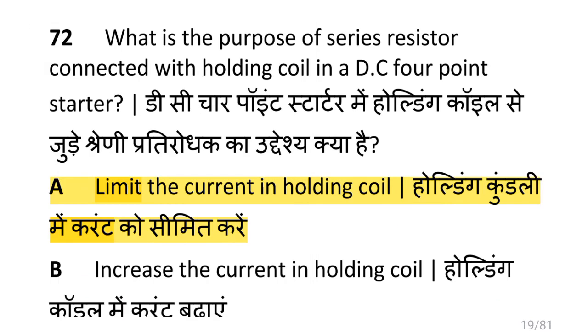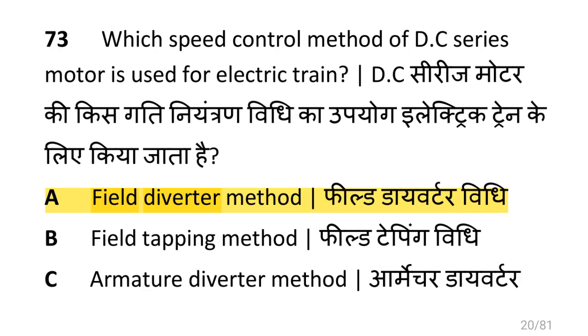What is the purpose of the series resistor connected with holding coil in a DC four point starter? That is to limit the current in the holding coil. Which speed control method of DC series motor is used in electric trains? That is the field diverter method.